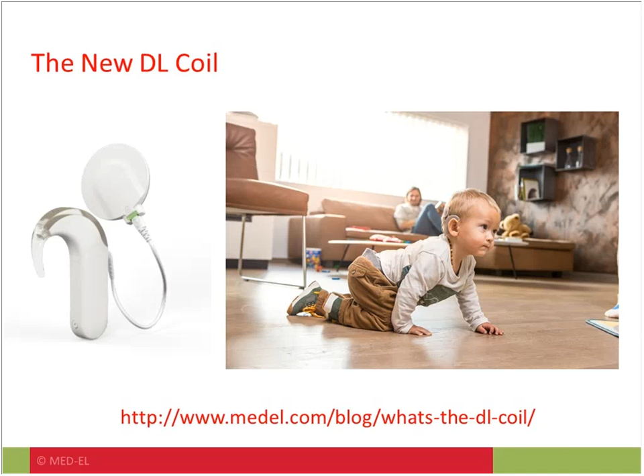If the coil has totally shut off, as indicated by the red light blinking every 10 seconds, you have to turn the processor off and on to turn the coil back on again. So it's a very simple way of checking that the device is connected and talking to the implant, or letting you know you need to troubleshoot something.